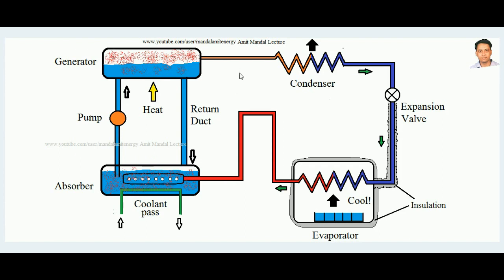In the absorber, ammonia is absorbed in liquid water forming a strong solution. When sent to the generator and heat is added, ammonia is liberated leaving a weak solution, which returns to the absorber via a return duct. This is the cyclic process in the generator-absorber system. To keep the absorber water cool, a coolant is supplied through a heat exchanger arrangement, removing heat so the water remains at a low temperature.